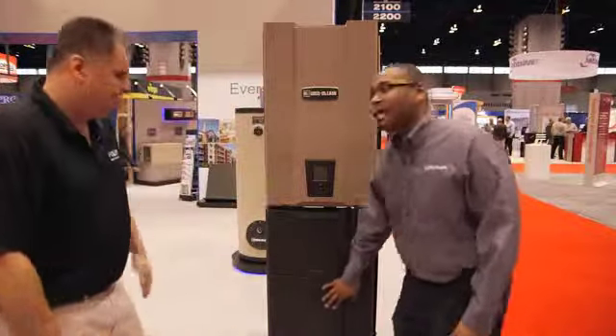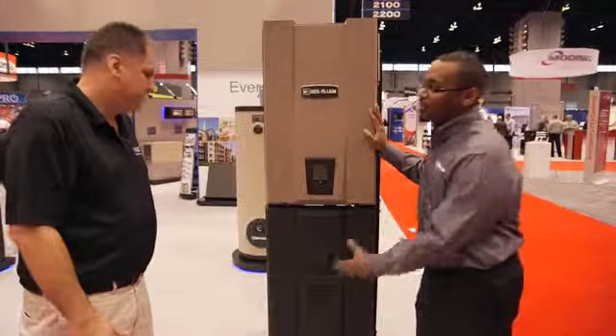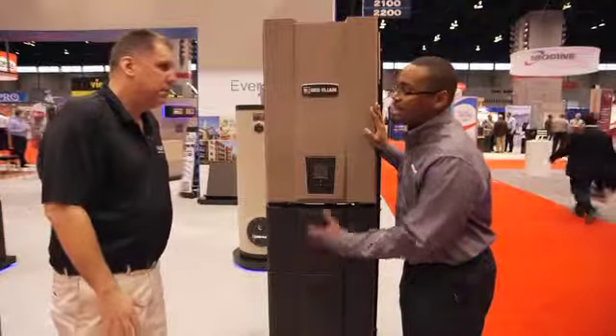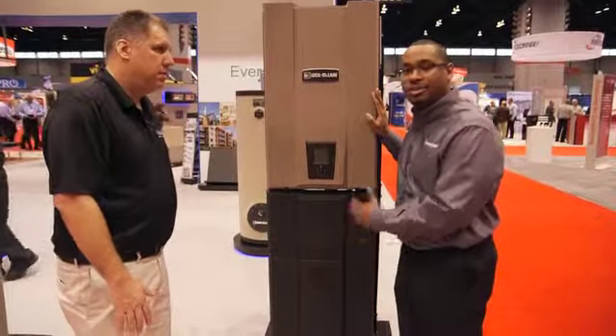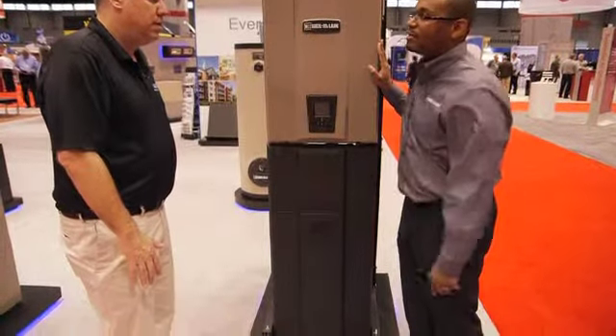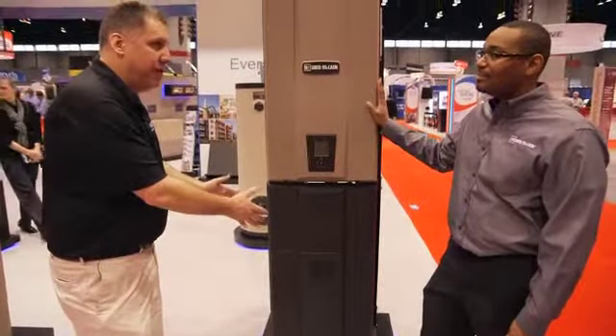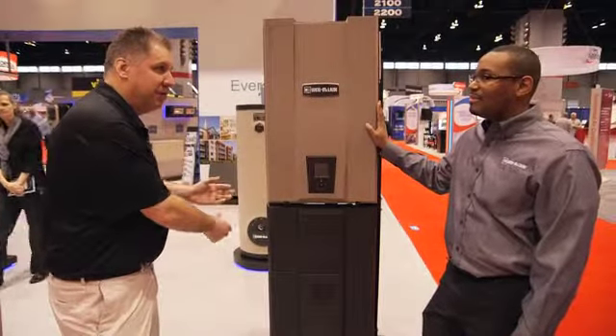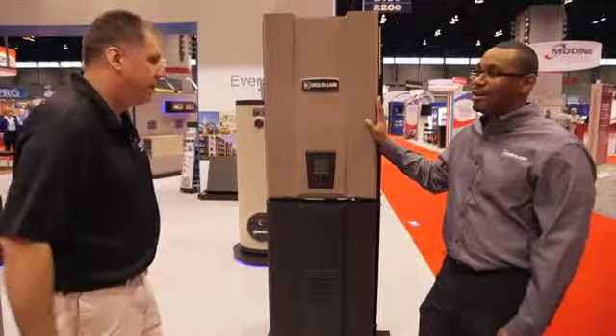What is this device? Yeah, so this is our Aqualogic system. It's built just for this boiler. It has 2 sensors in there so that it has a fast recovery, and you can hold water in there at a higher temperature because it's 316L stainless steel, and it behaves like a 35-gallon tank, but it's only 18 gallons. So if you're storing it at 170, then we're going to have some type of external mixing valve or anti-scald valve. That's correct. It comes in a box. That comes with it. I don't need to provide it. No. That's great.